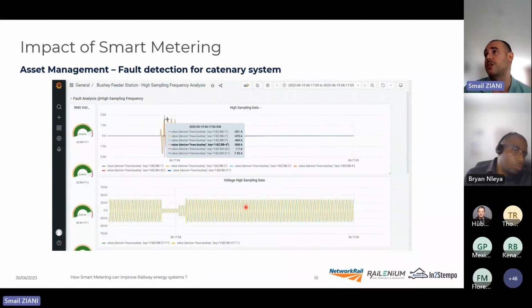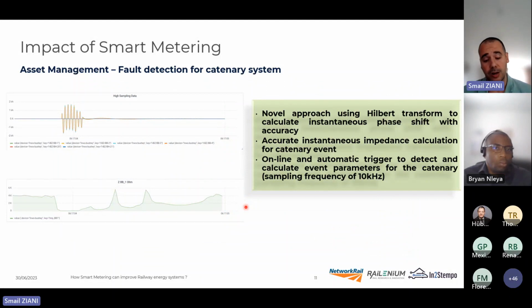So for the fault detection of the catenary system, we will use the data from the database, and we use Python to apply some novel approach to have a better accuracy for the calculation of the impedance, because the impedance is a very important indicator to understand better what kind of fault we have. So we use an instantaneous phase shift to have an instantaneous impedance. And we use, of course, Python to do it.